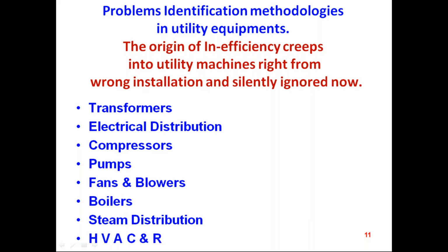What is the loss between the HT and LT that we see in the transformer, and what is the distribution loss? Normally, in the industry, let us say it's a 1000 kVA transformer, the industry is loading around 800 kVA. Almost 800 units per hour we are taking.